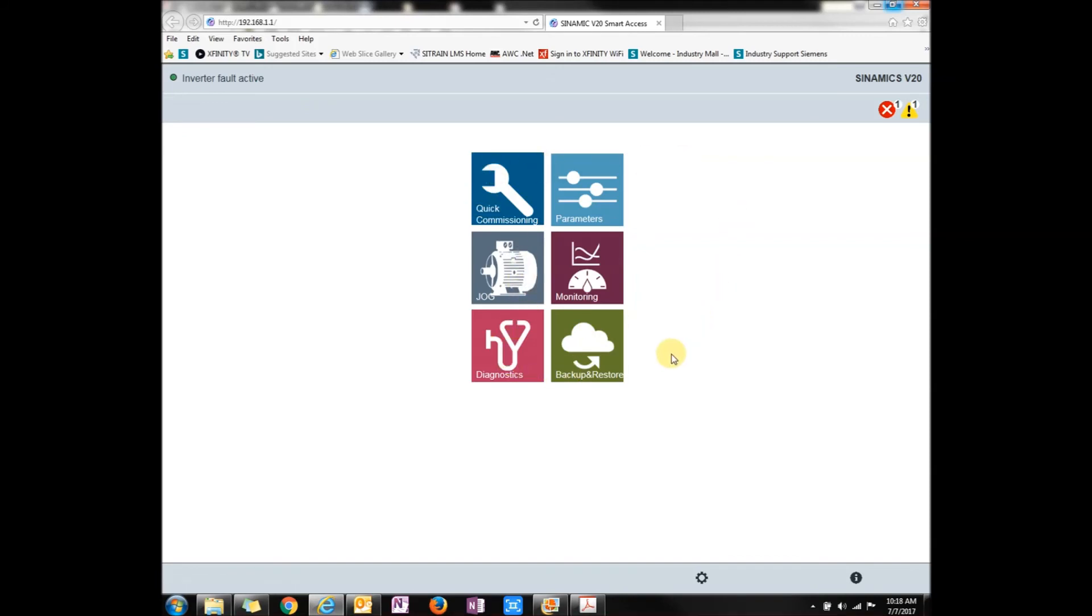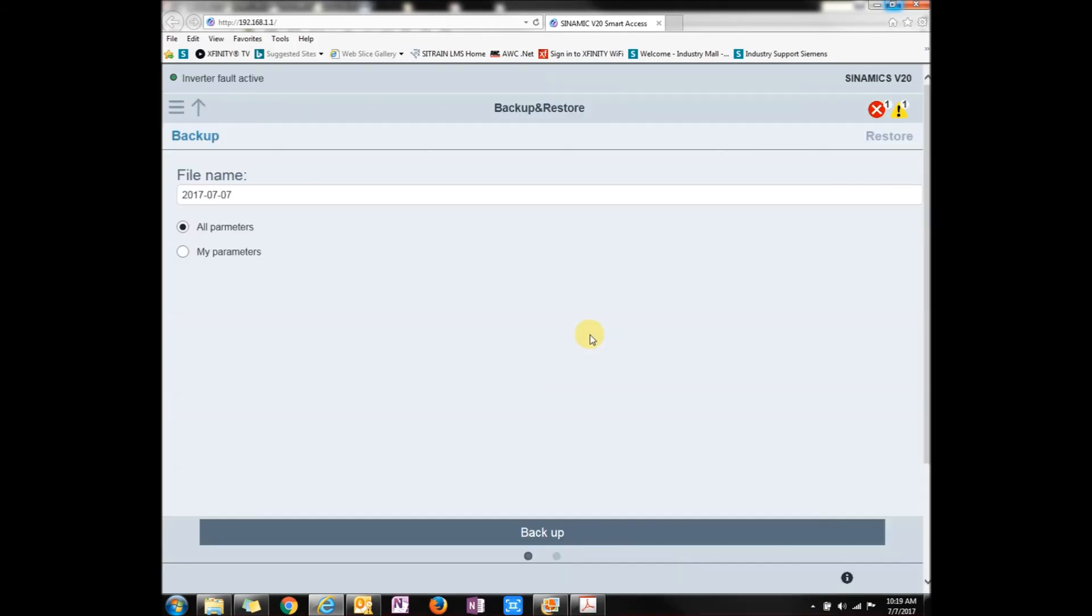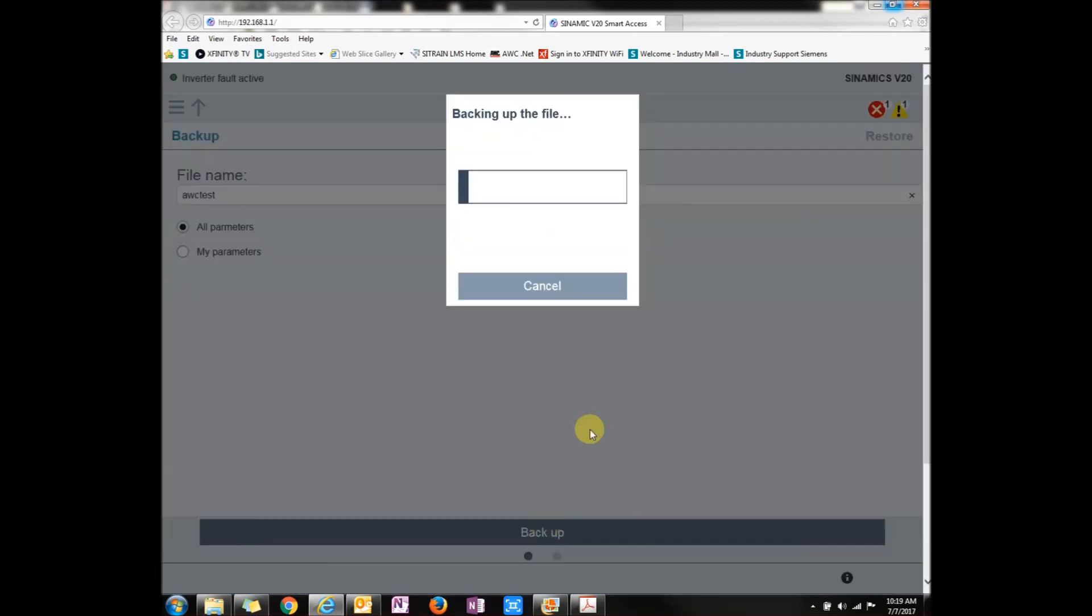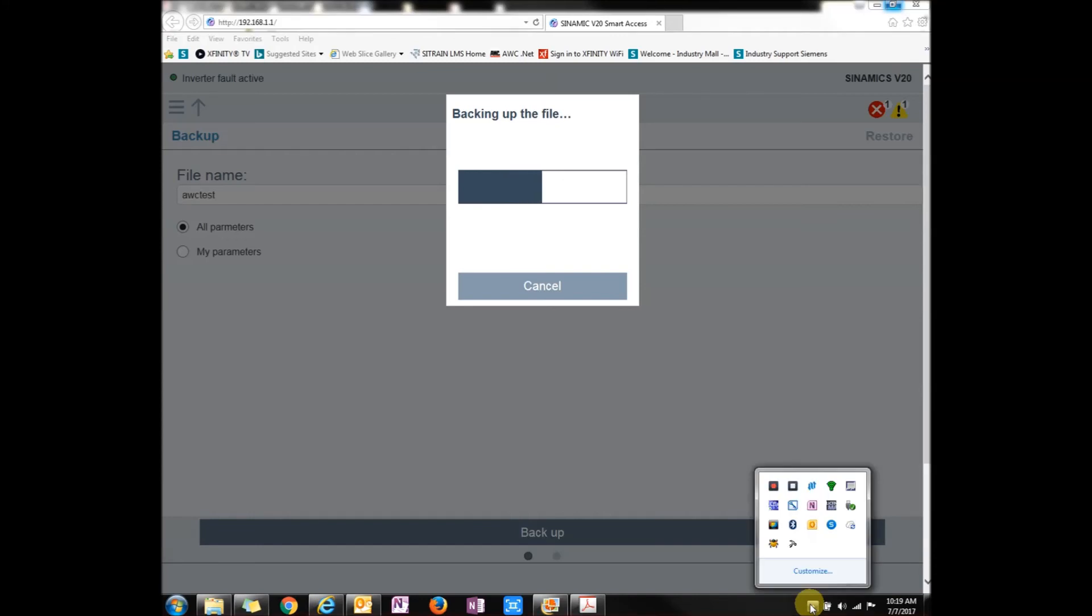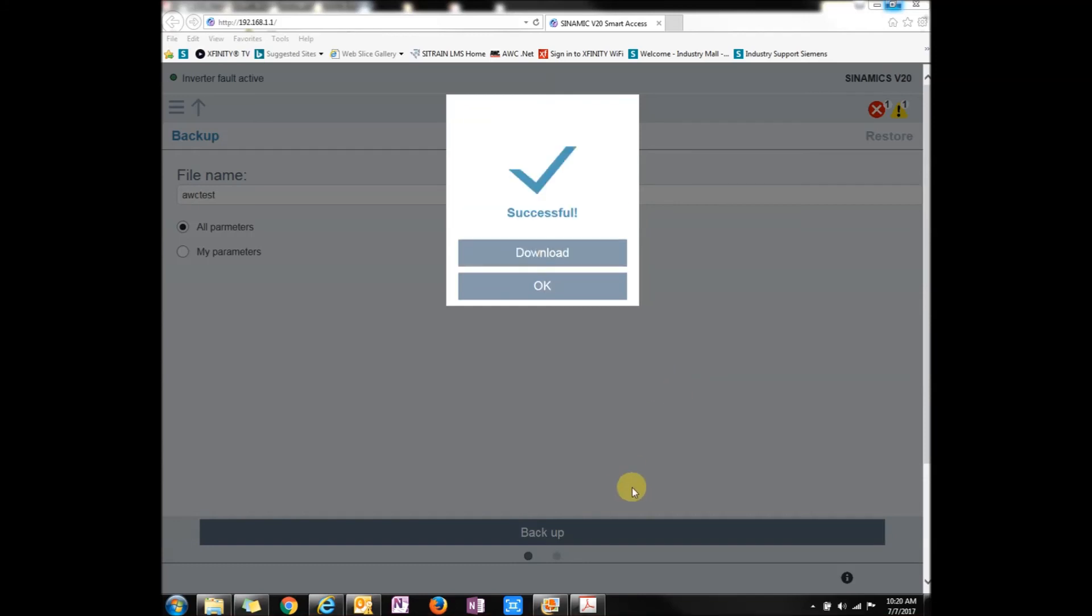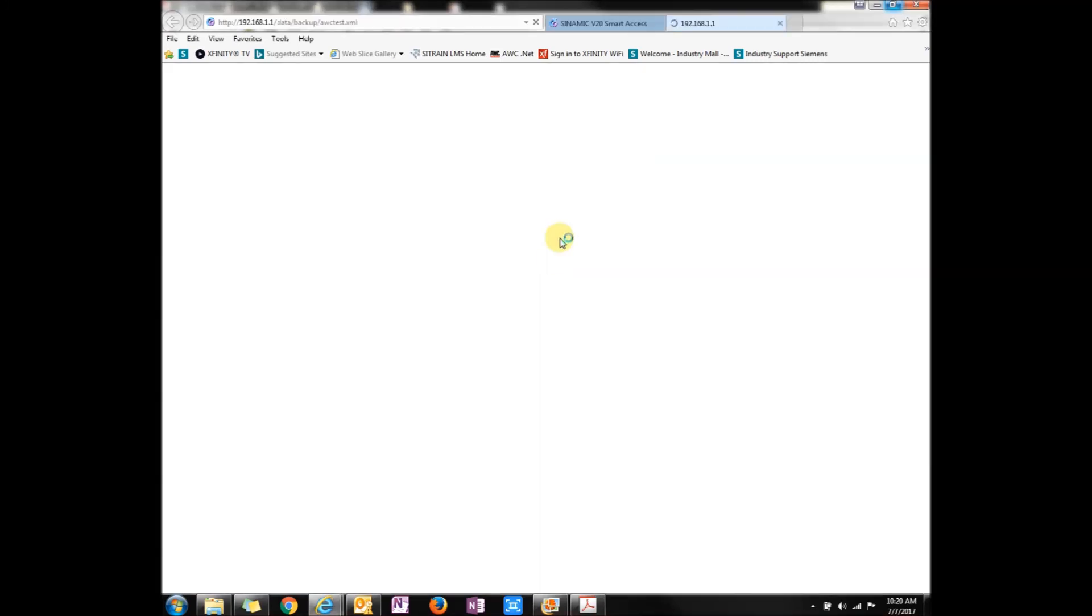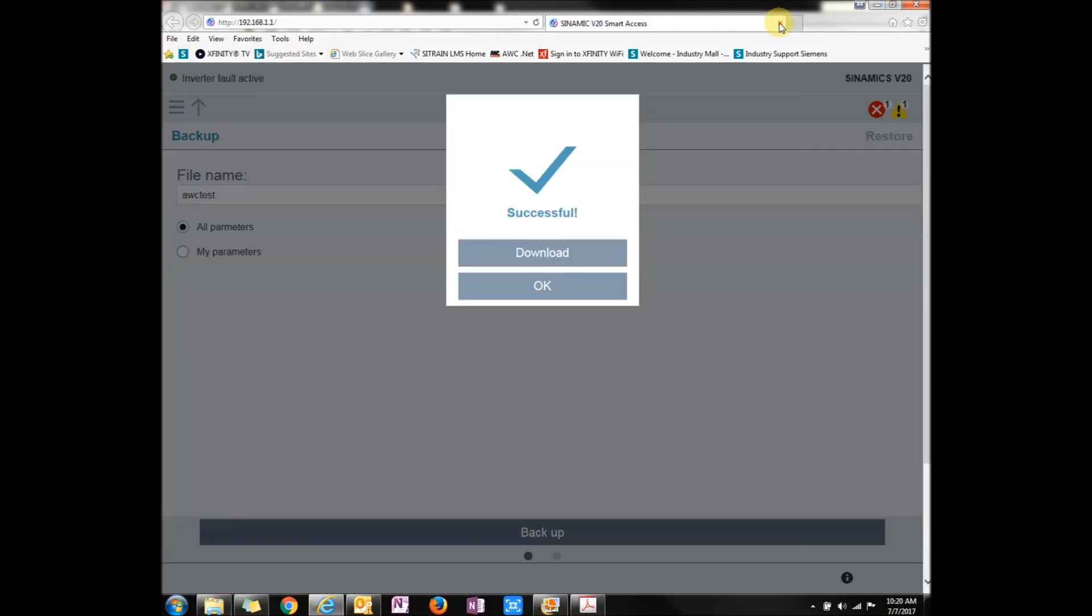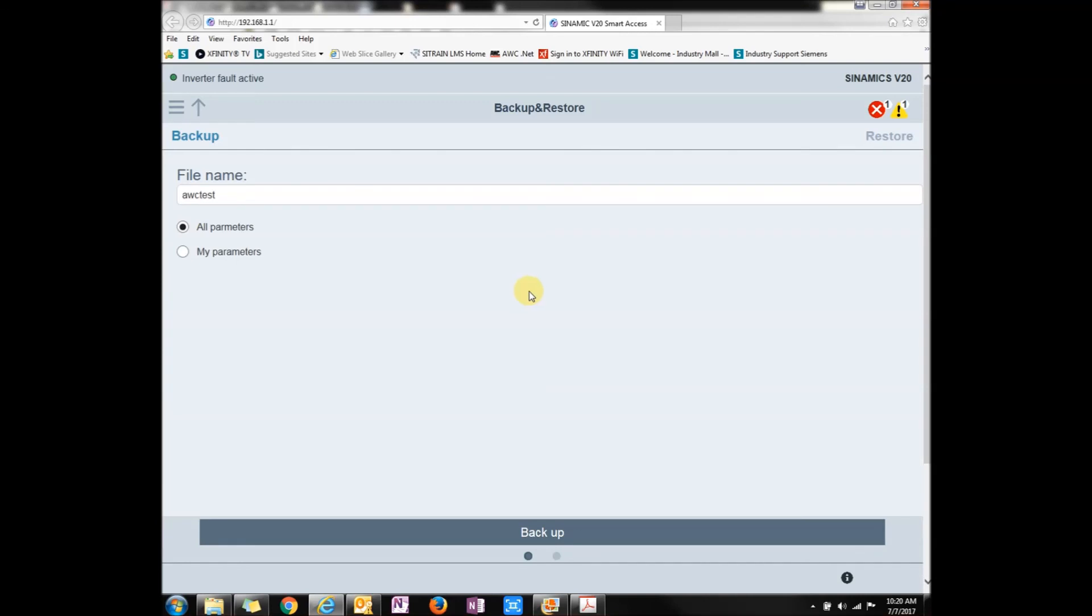One last thing I want to show you is the backup restore. As you can tell, you can either rename the file to whatever you want or just today's date. You can type in AWC test. But one caveat to this is you can't put any spaces in between. It kind of gets mad, so you need to make sure it's all together. Then you just press backup. Simple. This will take a little bit, so I'm going to speed up. And it was successful. Now, you can press OK or download, which brings up the screen for an XML file. But if you just press OK, it actually saves it to the Smart Access module itself.